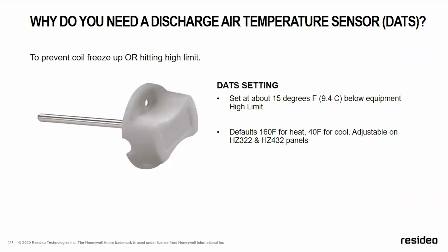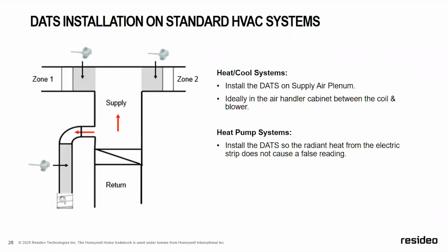And again, the panels default at 160 and 40. So if you're doing high static systems like a Unico or a Space Pack, you're going to want to go to the HZ322 or the 432 so you can make the adjustments. It is adjustable. Our panels are adjustable in 5-degree increments. Now, this is a little controversial, and our installation instructions, this is where they tell you to put the discharge air temperature sensor.